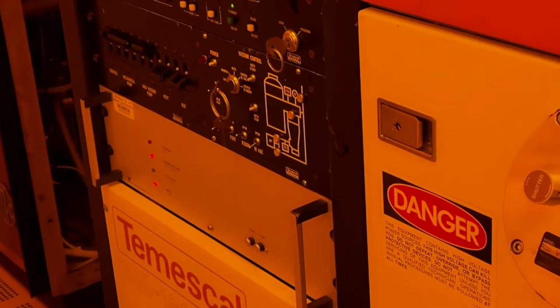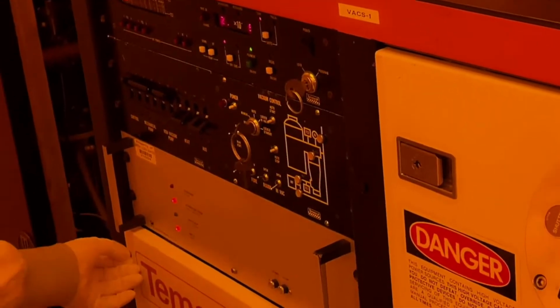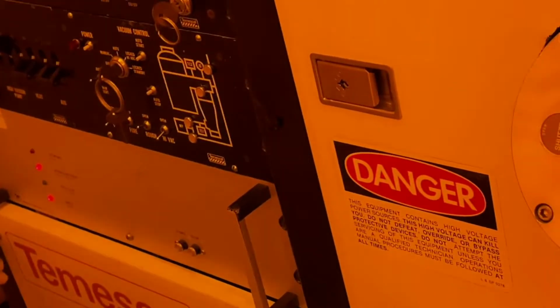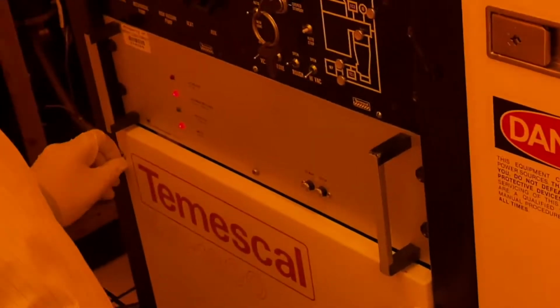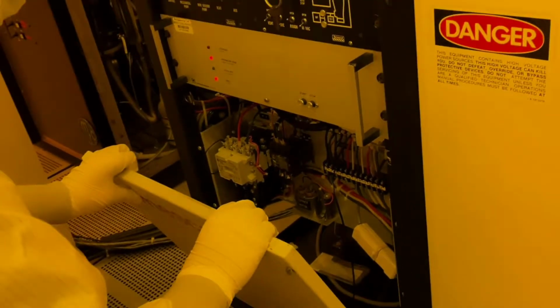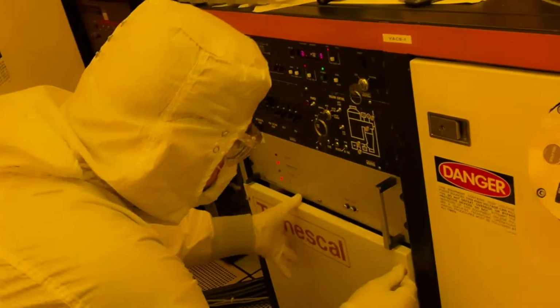Additionally, it's possible that with extreme power outages, the mechanical pump will also get knocked off. In that case, there is a reset right here. This is the motor control reset. This has happened before where basically this button will pop out. If the mechanical pump isn't running, you can just press this back in and it will restart the mechanical pump. That's most of the problems that you'll encounter with a power outage.